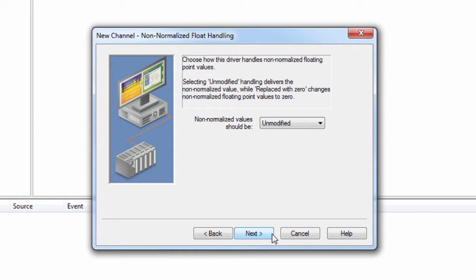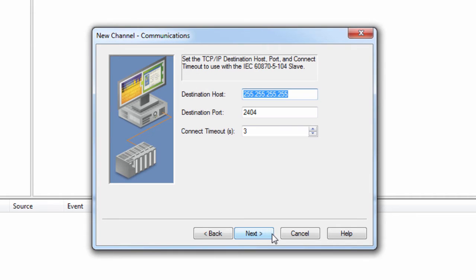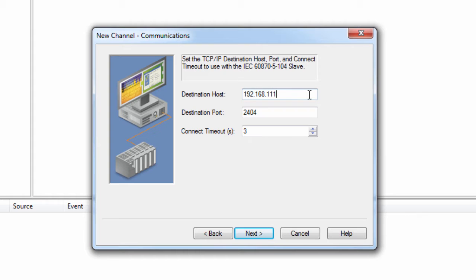Click Next to set the IP address of your device or gateway. This will be entered as the destination host. The destination port can usually be left at default since 2404 is considered the recommended port for this protocol. If your device is using another port besides the recommendation, you would enter that here. The connect timeout should be left at default. It can be changed later if needed.